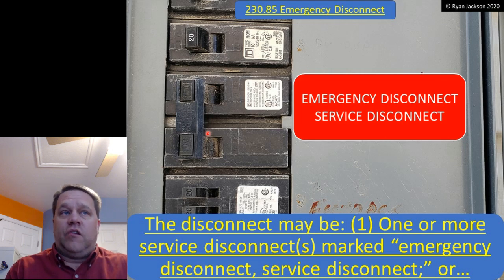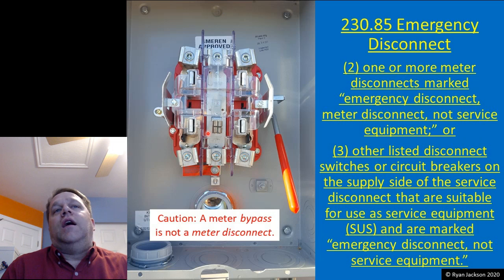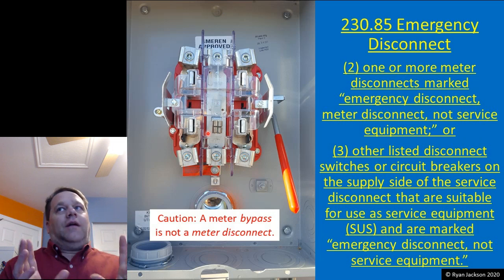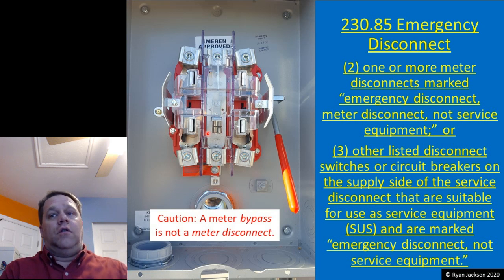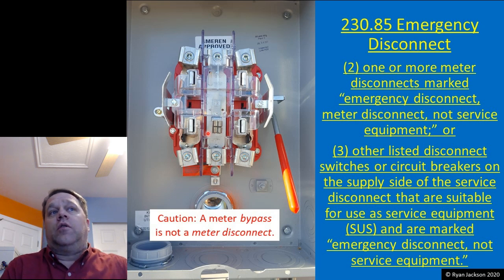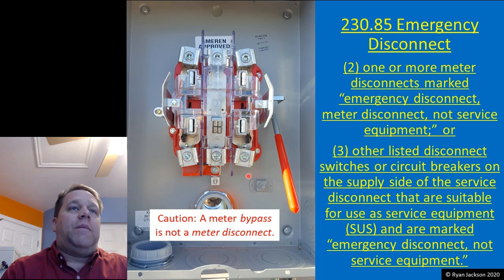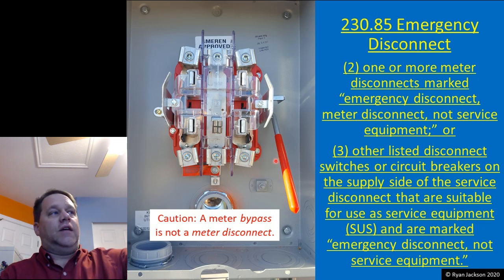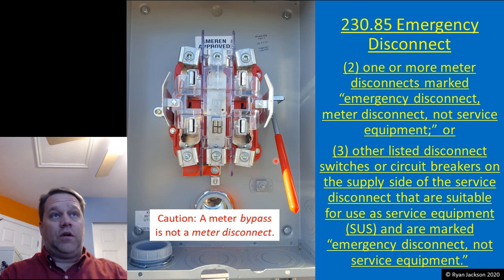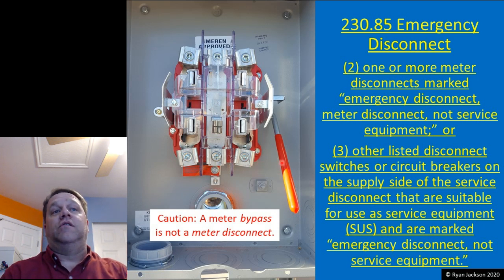There are other options. I can use a meter disconnect. Now, I have never seen, and to be honest, I've never even heard of a meter disconnect at a house. This thing in the photograph is not a meter disconnect. This is a meter bypass. So let's be very clear on that. A meter bypass is not a meter disconnect. A meter disconnect shuts off the power, right? A meter bypass does the exact opposite. A meter bypass leaves it on.